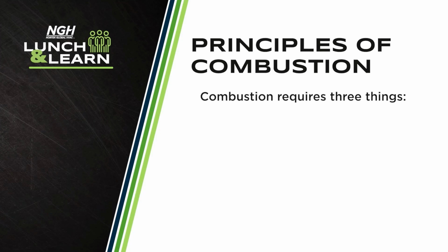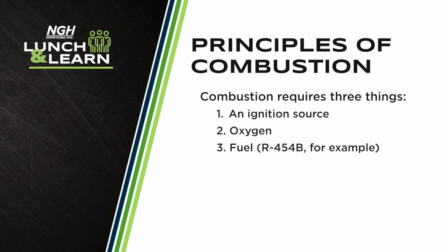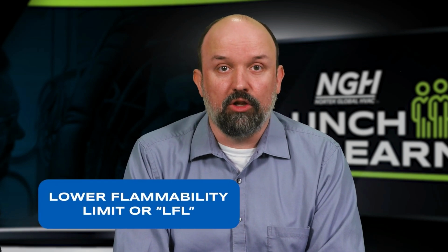First, we need to understand some principles of combustion. Combustion requires three things: an ignition source, oxygen, and fuel. In our case, R454B is the fuel. When a gas is the fuel, there is a minimum concentration required for combustion. We call this the lower flammability limit, or LFL.